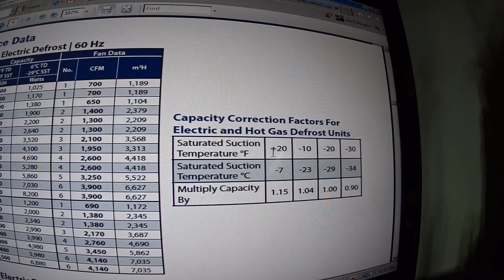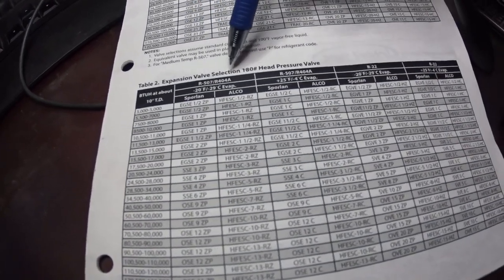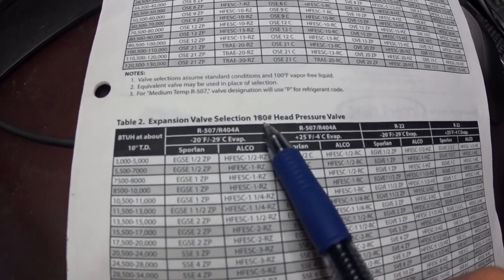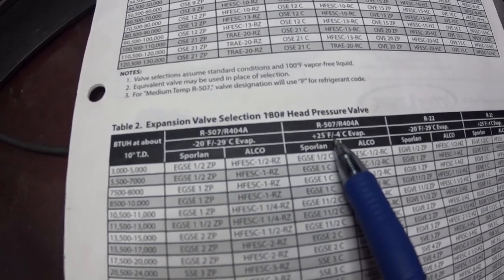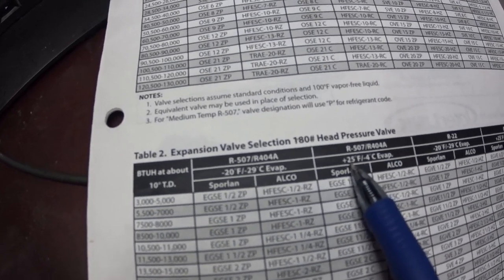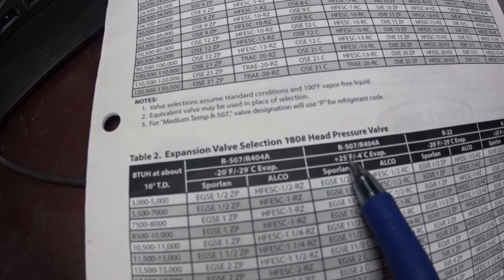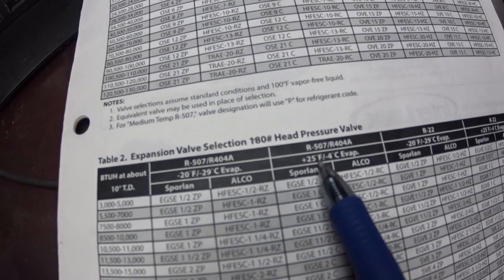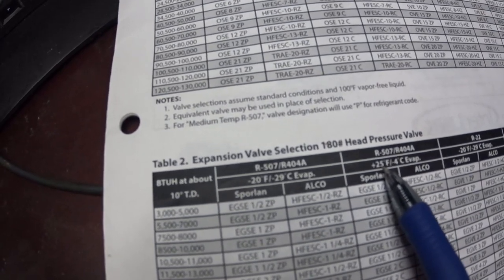The saturation suction is 20 degrees. For expansion valve selection, we're at 180 pounds — you can get the expansion valve at 100 degrees, but we're using 180. We want 404A and a 25 degree evaporator. Selections are usually done on 20 or 25 degree evaporator. The air temperature is usually 10 degrees colder in the box, so at a 25 degree evaporator you're shooting for a 35 degree air temperature, which is standard for a 38 degree walk-in cooler.